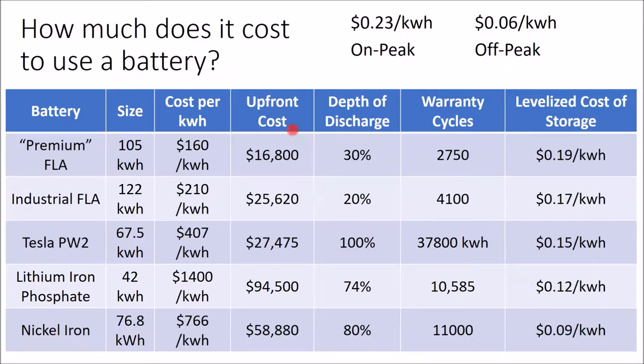So we're looking at two different lead acid battery banks, a top shelf and a mid-range - a larger bank used less versus a smaller bank used more. It turns out that the battery bank with the highest capital cost also has the lowest levelized cost of storage. But to use this industrial lead acid battery bank - and this does not include maintenance cost, and lead acid batteries have maintenance. You can get sealed lead acid batteries, but if you're getting those, you might as well get lithium ion, in my opinion, especially if you can hold out another year or so.